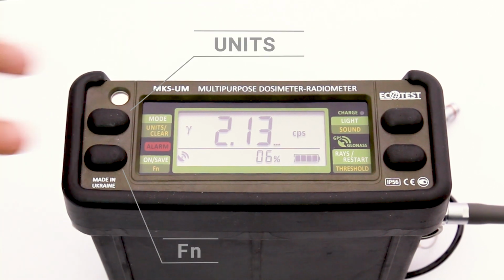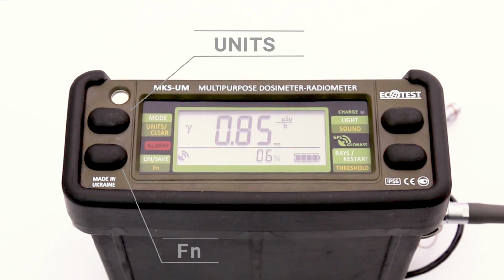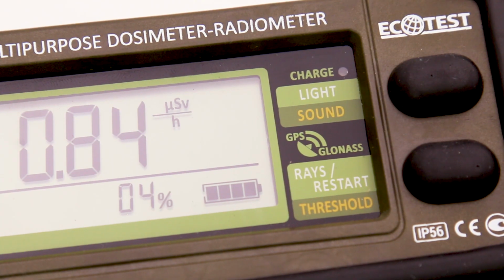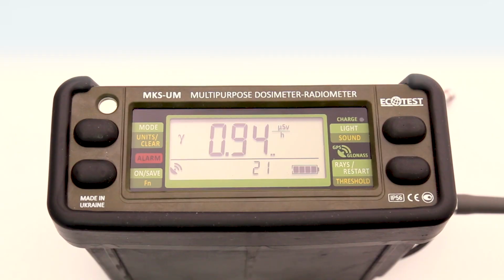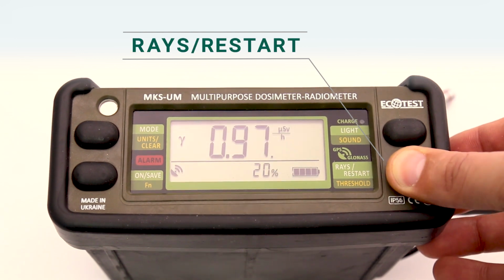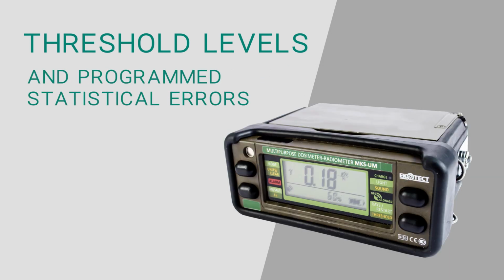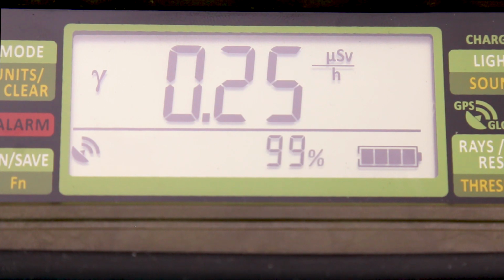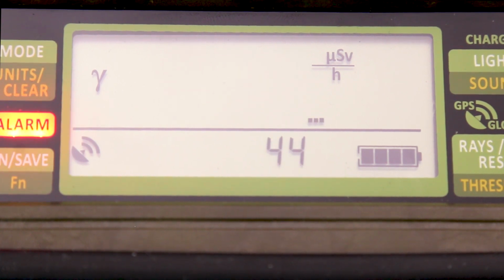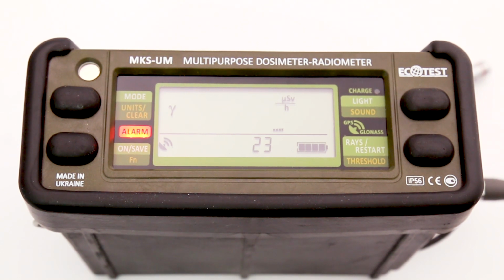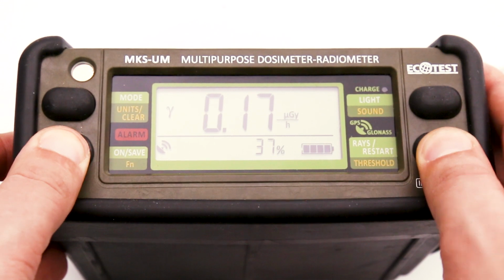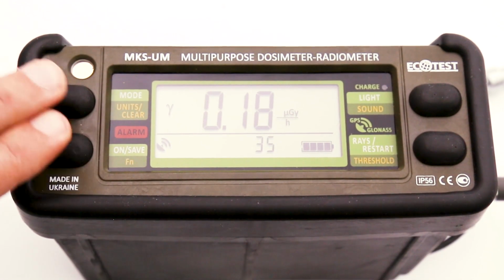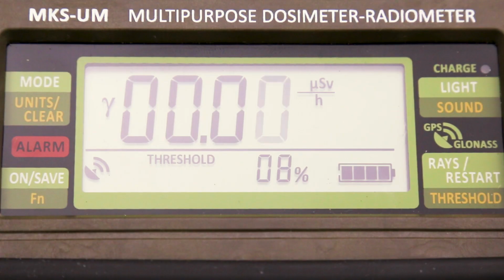Press FN and units simultaneously to change the units of measurement. The measurement results are updated with an interval of 2 seconds. The measurement process can be restarted at any time by pressing Rays/Restart briefly. The light and sound alarms will be activated if the dose rate threshold is exceeded. The device operates with 3 independent threshold levels, and different threshold values can be set for each level. Setting the 0 value disables the alarms.